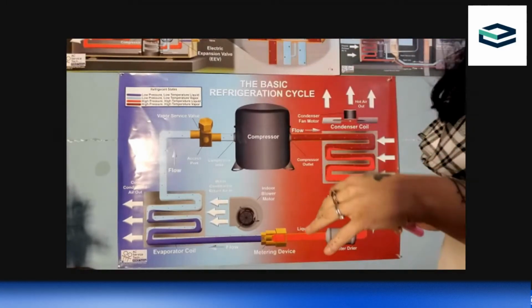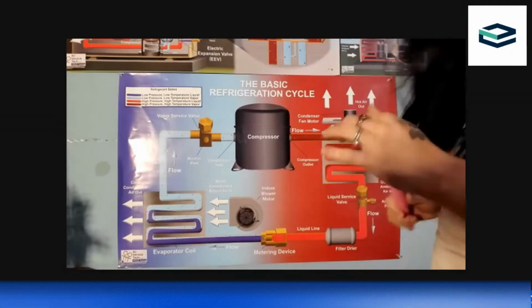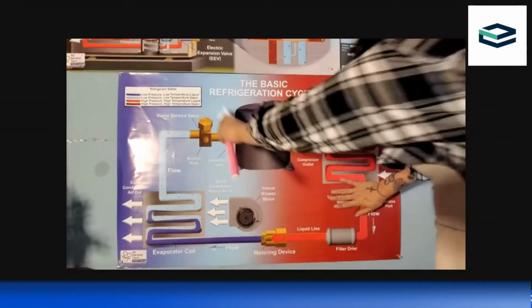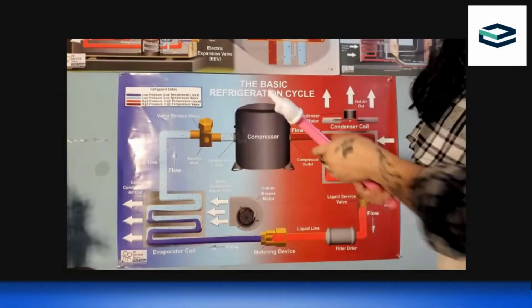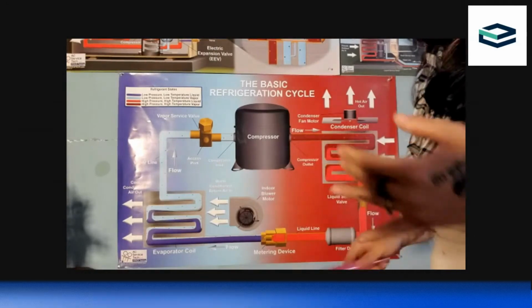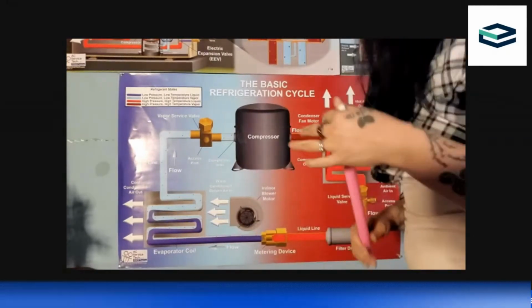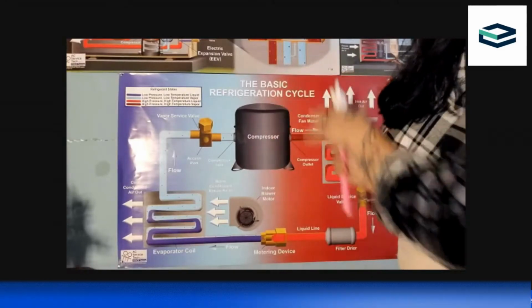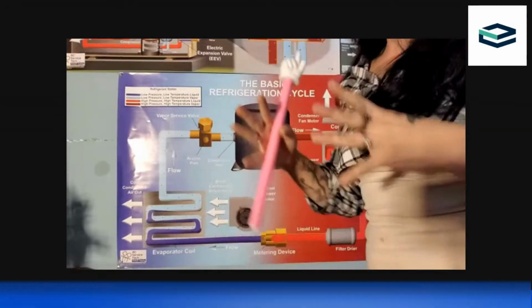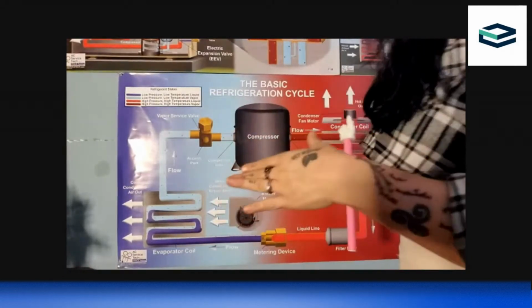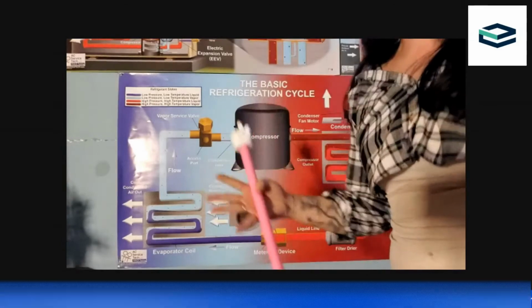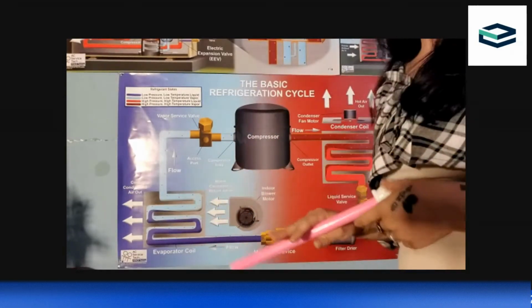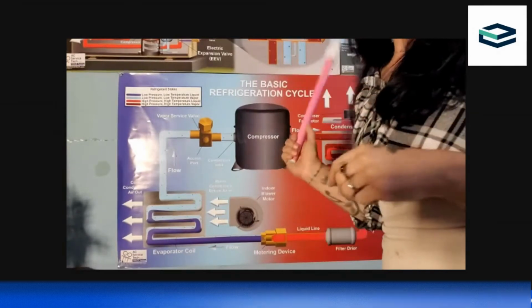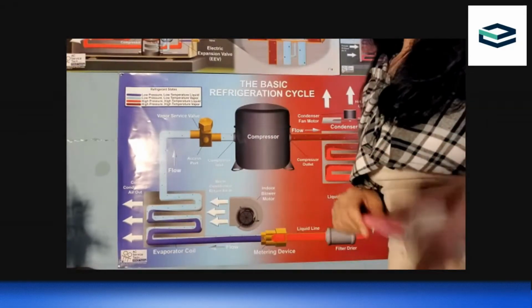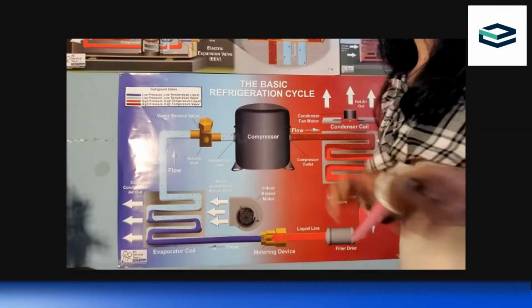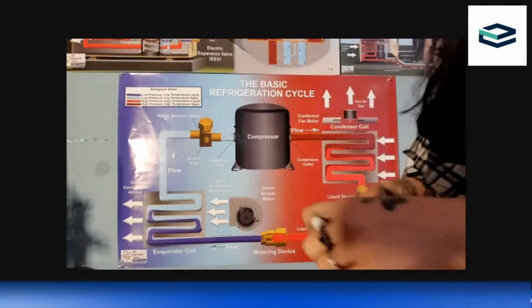So the next thing that I want to talk about is superheat and subcool. There are systems, like we talked about before, that only have one valve to gauge up to. When that's the case, you will go without either your superheat or your subcool. Usually subcool is what you have, sometimes not. But if you're going without your superheat or your subcool, you can still tell based on one or the other. Your superheat and your subcool are nothing more than a calculation. We used to have to do that by hand using pressure temperature charts. Now we don't have to because our manifolds do them or our JobLink does them. It's still a good thing to know. Maybe Encompass can do a little short to teach you guys how to calculate subcool and superheat. I'm not going to do that right now.